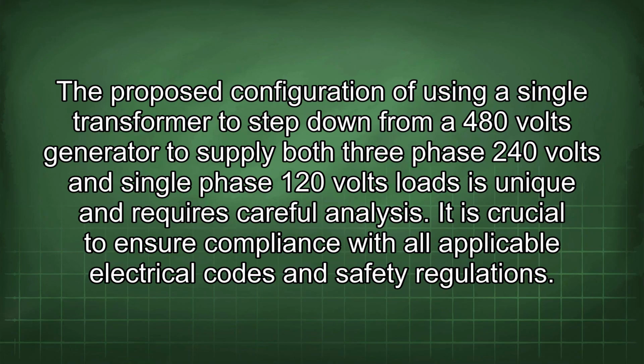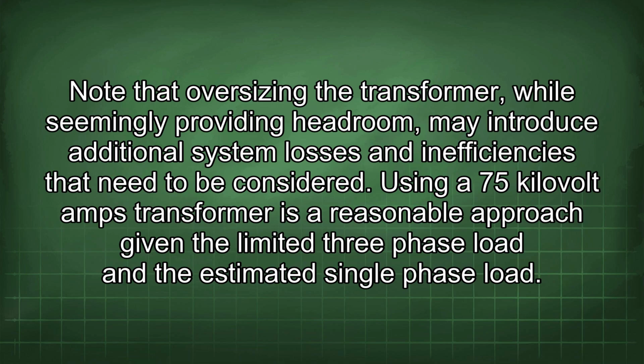The proposed configuration of using a single transformer to step down from a 480 volts generator to supply both three-phase 240 volts and single-phase 120 volts loads is unique and requires careful analysis. It is crucial to ensure compliance with all applicable electrical codes and safety regulations.